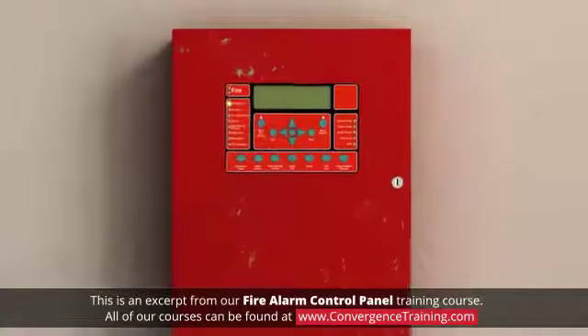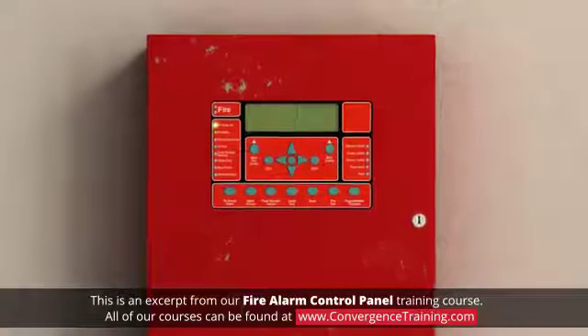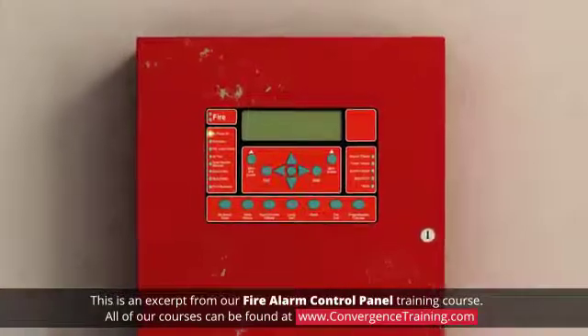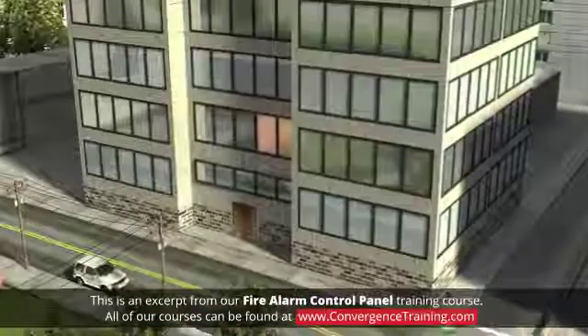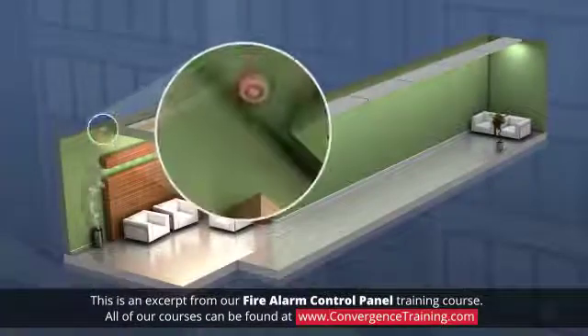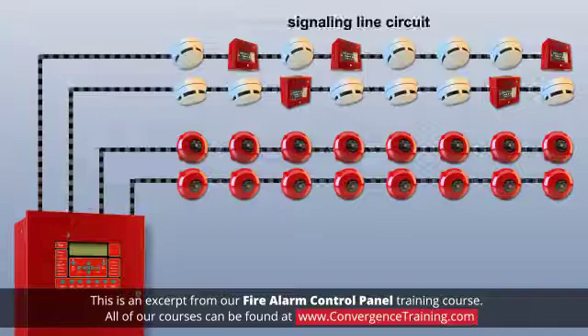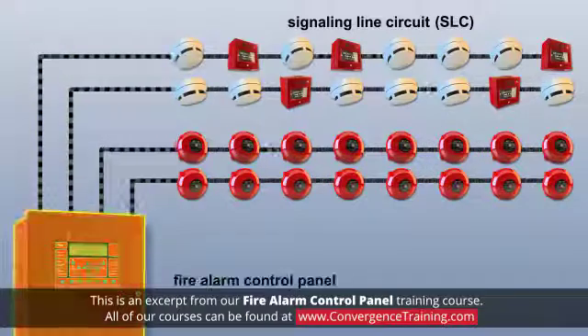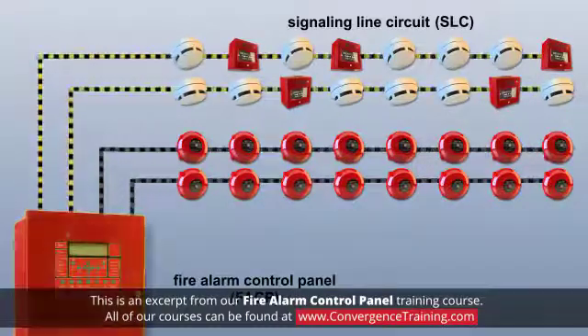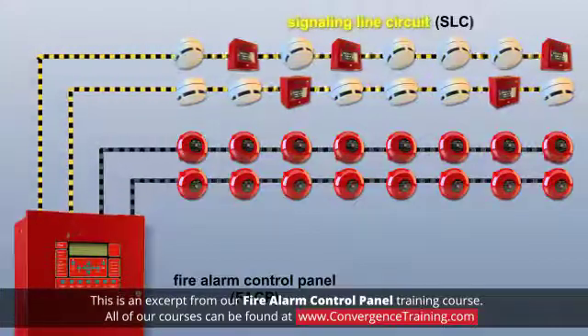Addressable systems use advanced technologies and detection equipment for discrete identification of alarm signals at the detector level. An addressable system can pinpoint an alarm location to the precise physical location and the type of initiating detector. Each component on the signaling line circuits, or SLC, has an identification number or address. The fire alarm control panel, or FACP, constantly checks each device using a signaling line circuit, or SLC.